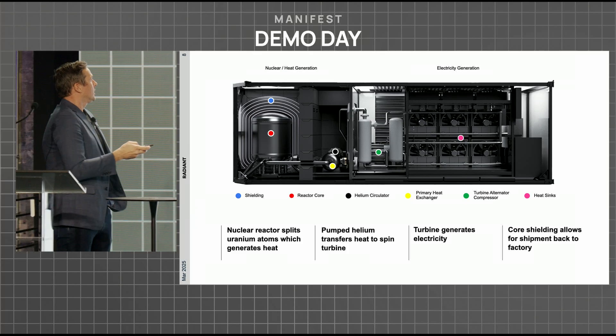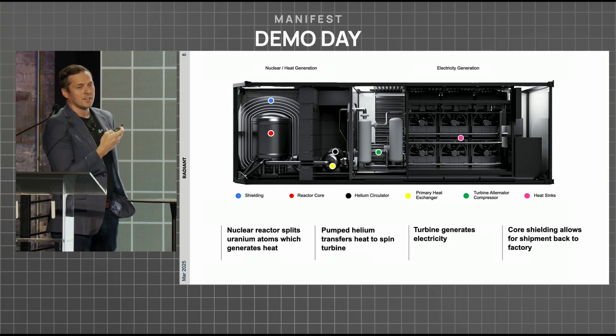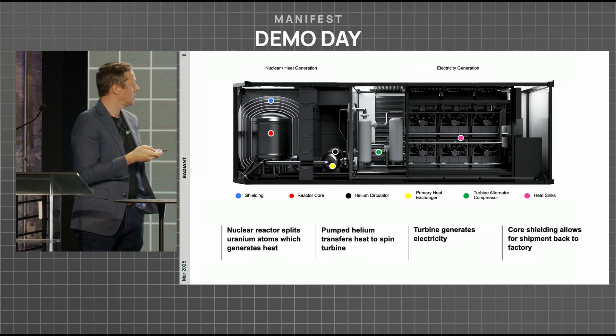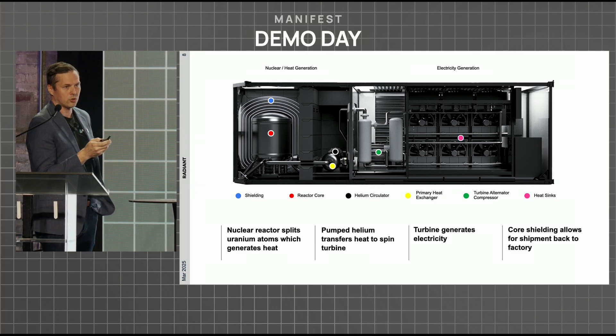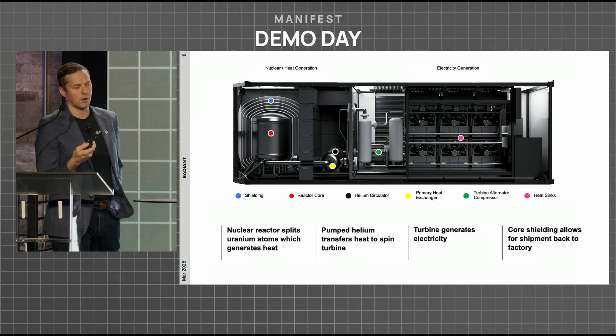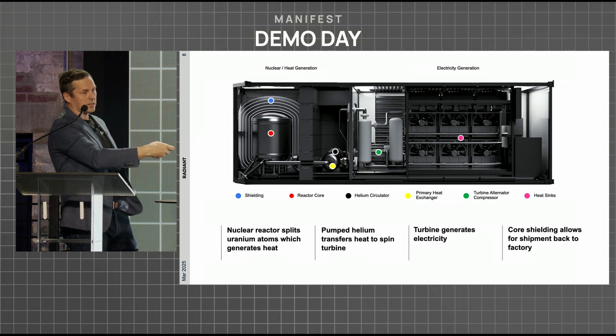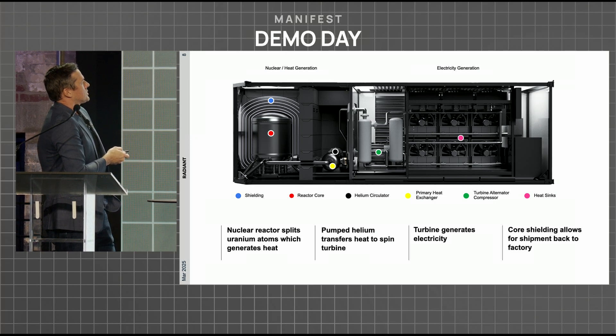So how do we make this work? You've got a stainless steel pressure vessel that weighs about eight tons. Inside of that we've got precision-machined graphite and nuclear fuel inside a core. There are actuators under it that rotate control blades in and out to turn the reactor on and off and control power generation. There's shielding around the unit inside the package, and that's used so that you can meet transportation regulations from the Department of Transportation. That allows you to shut down a reactor and then 30 days later ship it down normal public highways in the U.S.